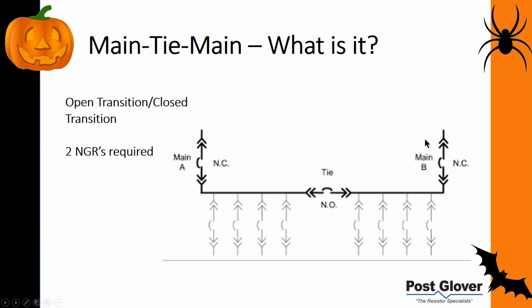So what does this do? It gives you flexibility, as you can see with loads on both sides. Ideally you're running two separate systems, but let's say main A goes down—you would close the tie breaker, and you could support those loads with the secondary source, or at least support some of those loads.